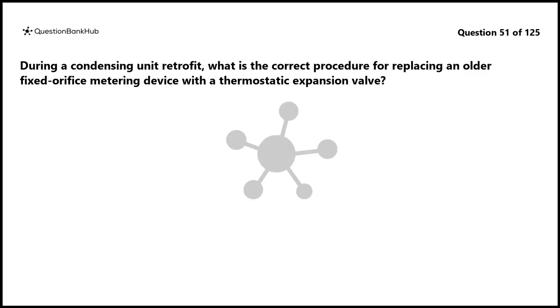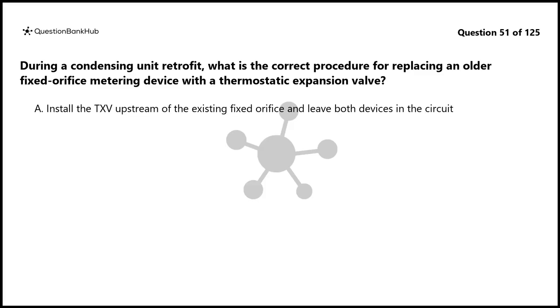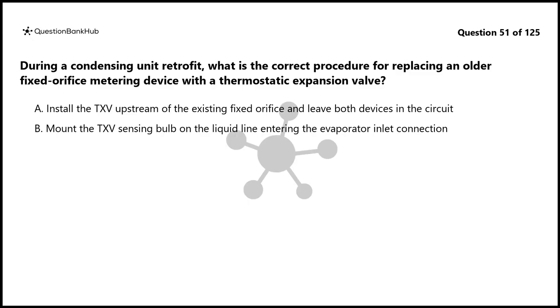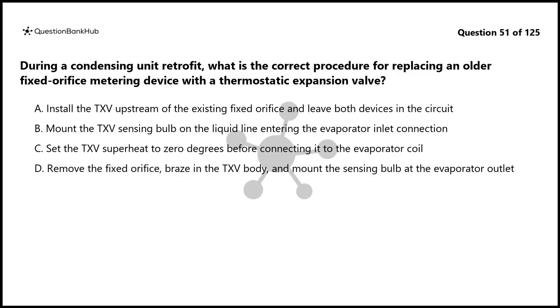Question 51. During a condensing unit retrofit, what is the correct procedure for replacing an older fixed orifice metering device with a thermostatic expansion valve? A. Install the TXV upstream of the existing fixed orifice and leave both devices in the circuit. B. Mount the TXV sensing bulb on the liquid line entering the evaporator inlet connection. C. Set the TXV superheat to 0 degrees before connecting it to the evaporator coil. D. Remove the fixed orifice, braze in the TXV body, and mount the sensing bulb at the evaporator outlet.